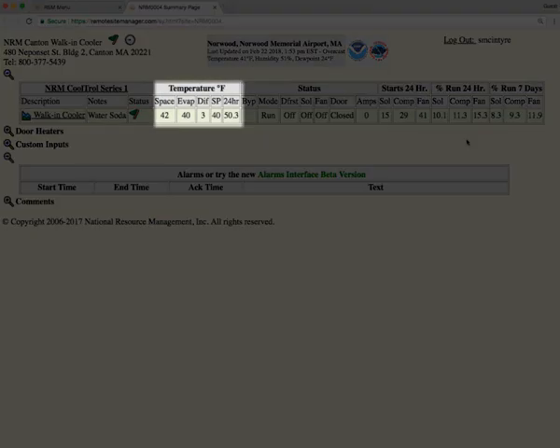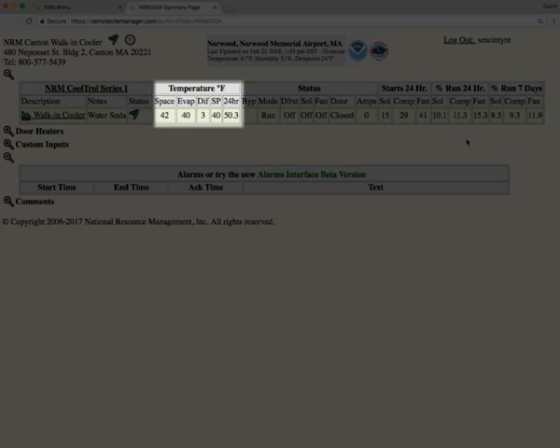Temperature section. Each controller has a space temperature and an evaporator temperature. The space temperature is used for the controlling of the refrigeration. That's the temperature that the refrigeration will turn on and off with. The evaporator temperature is used to know that it's safe to shut the fans off, diagnosing purposes, and defrost purposes.